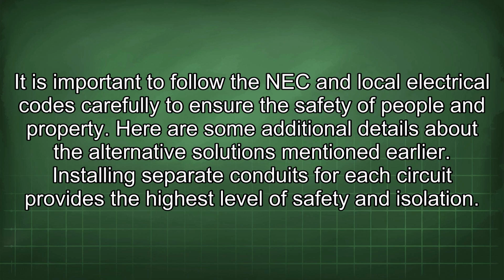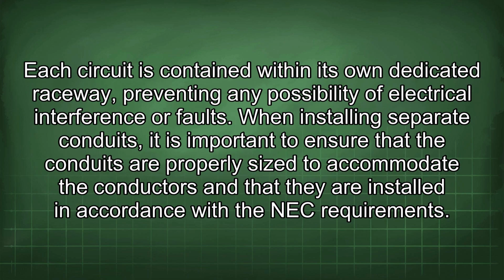Here are some additional details about the alternative solutions mentioned earlier. Installing separate conduits for each circuit provides the highest level of safety and isolation. Each circuit is contained within its own dedicated raceway, preventing any possibility of electrical interference or faults. When installing separate conduits, it is important to ensure that the conduits are properly sized to accommodate the conductors and that they are installed in accordance with the NEC requirements.